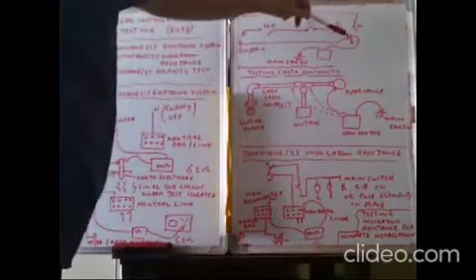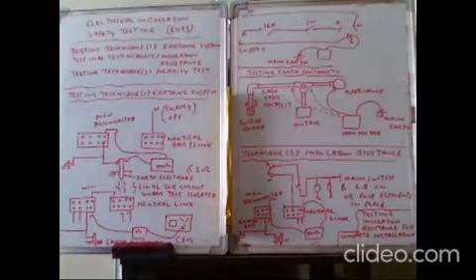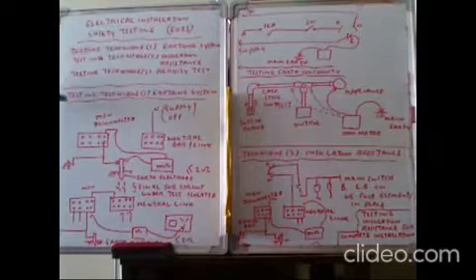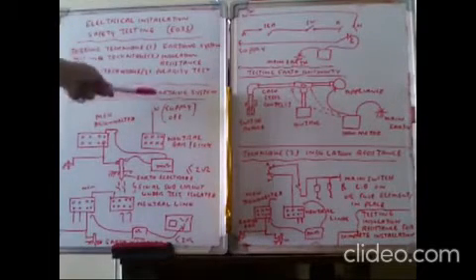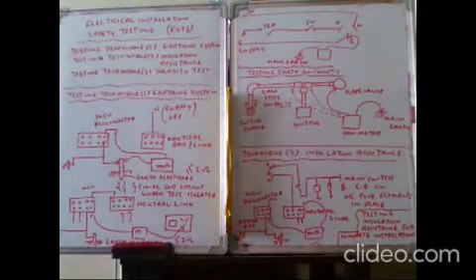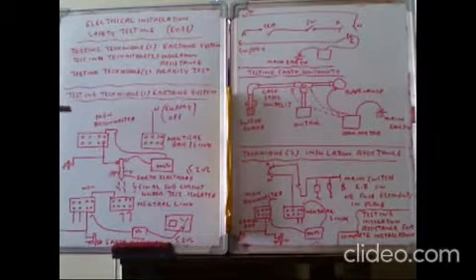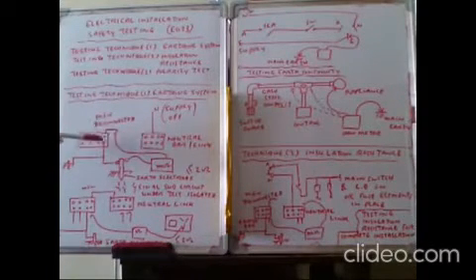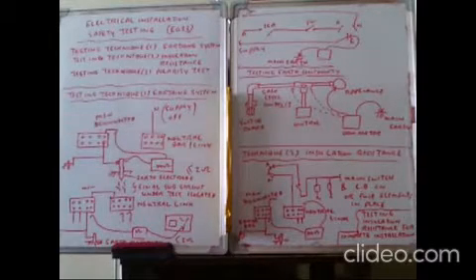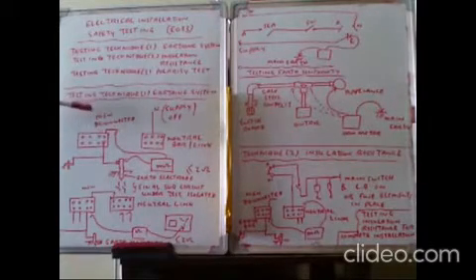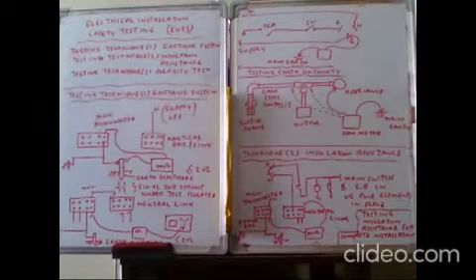There must be no wrong connection between the active and neutral wire. We test the earthing system, insulation resistance, and polarity. For the earthing continuity test: remove the neutral link, switch off the supply, disconnect all wires from the neutral link. Using an ohmmeter connected between the neutral link terminal and the earth connection link, resistance must be less than 2 Ω.